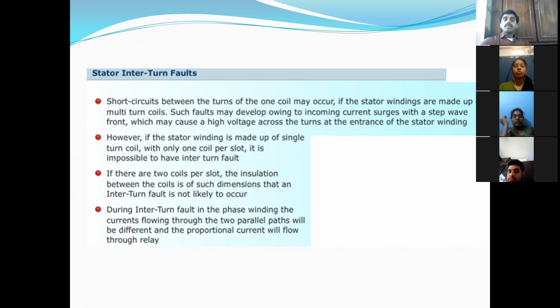Interturn faults means turn to turn fault occurs between the turns. Let us see a few salient points on this. Short circuits between the turns of one coil may occur, because one coil may have a number of turns. Between the turns, there may be a short circuit. If the stator windings are made up of multi-turn coils, there will be faults between the turns. Such faults may develop owing to incoming current surges with a steep wave front, which may cause high voltage across the turns at the entrance of the stator winding. So previously I have seen total winding fault. Now between the turns, the fault occurs.